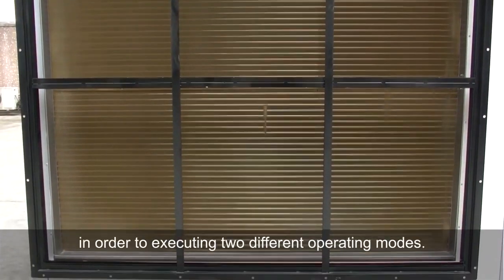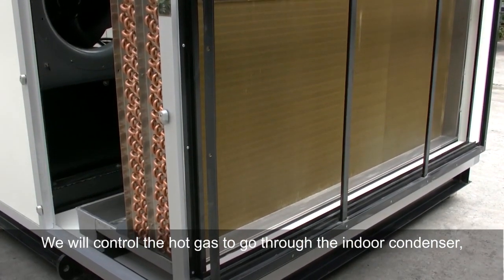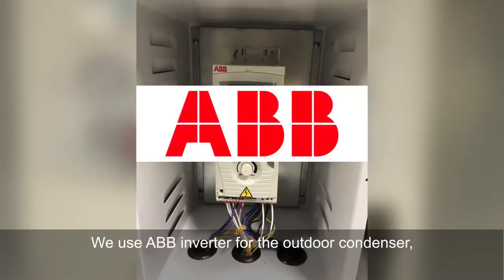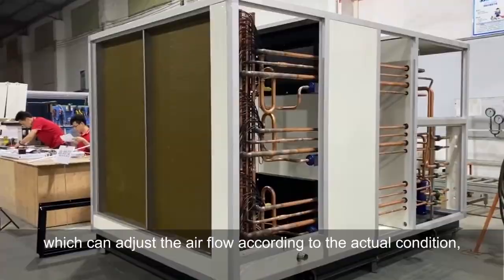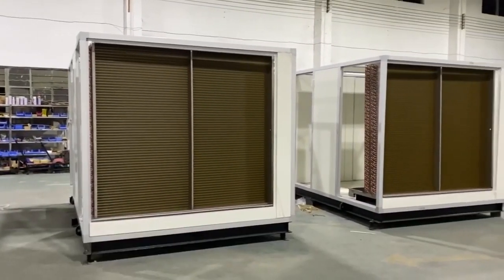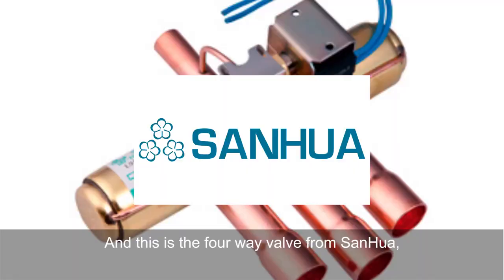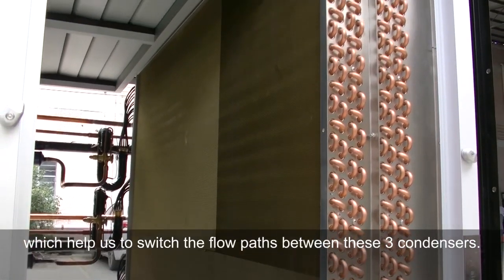We offer three condensers in this unit in order to support two different operating modes. If we want to supply warm dry air, we control the hot gas to go through the indoor condenser. If we want to supply cool dry air, the hot gas from the compressor goes through the outdoor condensing unit. We use an ABB inverter for the outdoor condenser, which can adjust the airflow according to actual conditions, running perfectly even in very low ambient temperatures. These three condensers are made of high-quality copper pipe and aluminum fins with anti-corrosion coating. A four-way valve from SanHua, the biggest supplier in China, helps us switch the flow paths between the three condensers.